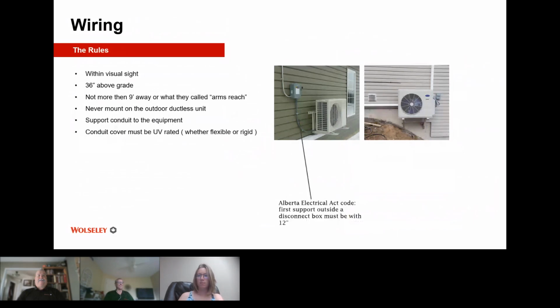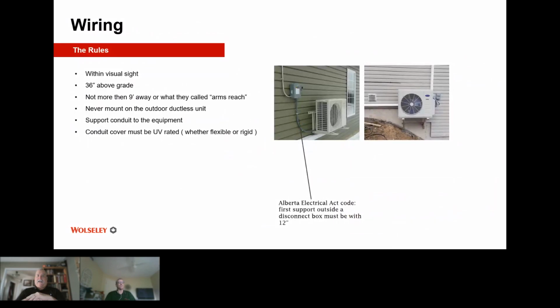Guys, these are some examples of great installations. Just want to make sure that everybody knows that, as I've alluded to before, and as was presented by Joey and by LG before, we want to get these units off the ground, on a stand or wall mount. If you choose to cover the line sets, as in the picture on the right with the line set cover, great. Try and keep these 3 feet away from dryers. Make sure that our outdoor disconnect is 3 feet above the grade, and this is specific to Alberta. Please consult your local code.